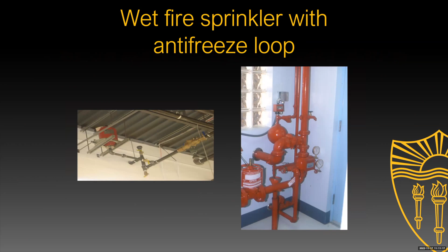There are two different types of antifreeze you normally hear about: propylene glycol and ethylene glycol. The difference is one is toxic and one is considered food grade. The food grade is propylene glycol; the toxic one is ethylene glycol. Propylene is less toxic, but it's more expensive. So even though people say to use propylene glycol because it's food grade, the fact that it costs a lot more means eventually people say this other stuff is cheaper and does the same job of keeping pipes from freezing, so let's put ethylene glycol in there instead, which is the more toxic substance.